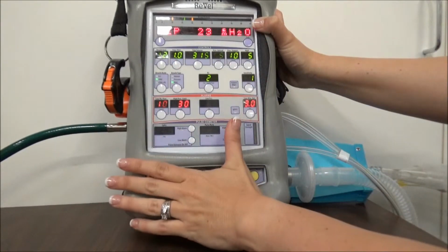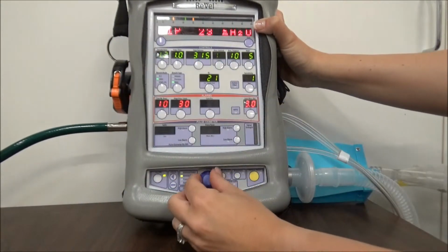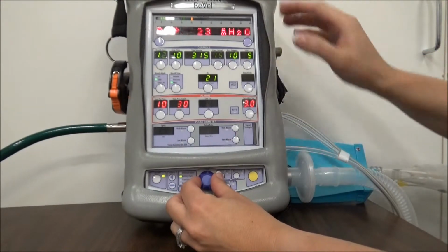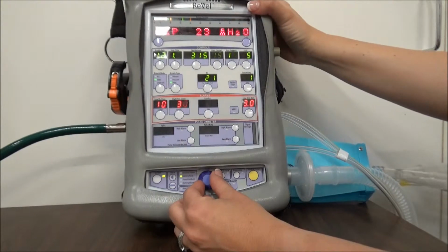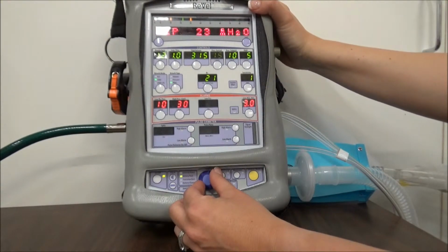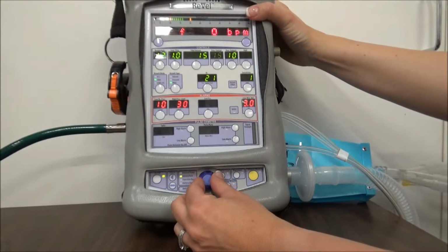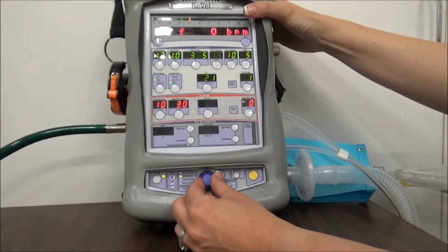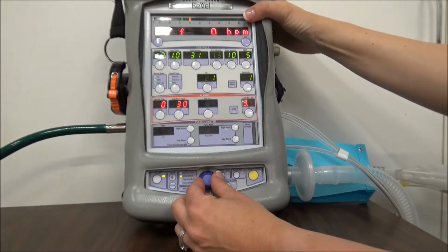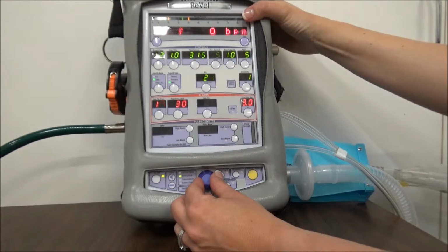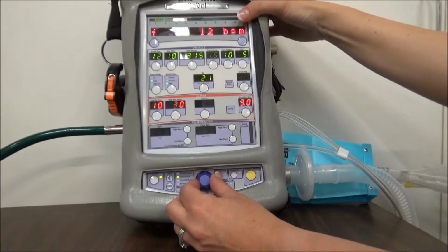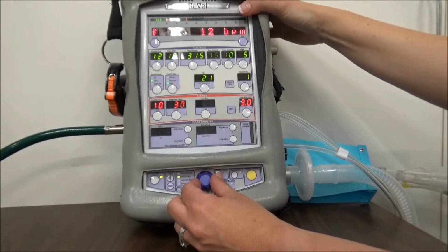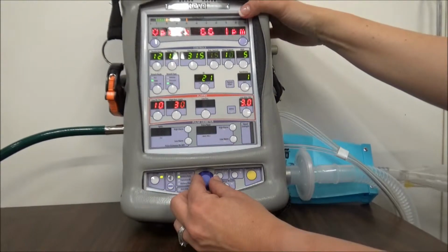So once we've chosen all that, I always tell people, once the front of the ventilator looks like you want it to, go back up here and start toggling through everything so you know where your normal values are before you start your transport. So you know where your peak inspiratory pressures are. Your spontaneous frequency is your spontaneous respiratory rate, so how much over the ventilator is your patient breathing. Your F is your frequency, that is your total, that's what the vent is doing for you.